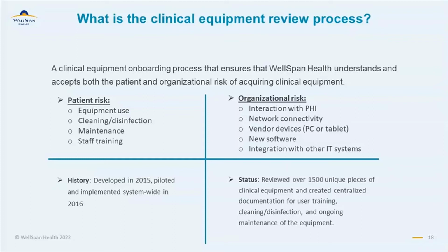We consider if PHI is processed, stored, or transmitted, and if so, what protections the manufacturer allows on their device to protect this PHI. We work really closely with our IT security team. They help us determine the security requirements for that device. And once we get that information back from that team, we actually will reach out to the manufacturer and we'll validate that they can meet these requirements. And if not, we often escalate to our senior management team, who must then determine if the benefit to our patients outweighs the risk to the organization, or if we should look for alternate equipment. We also factor in network connectivity requirements. Does the use of this equipment negatively impact our network performance? Will the equipment allow for system patching to protect against attacks?